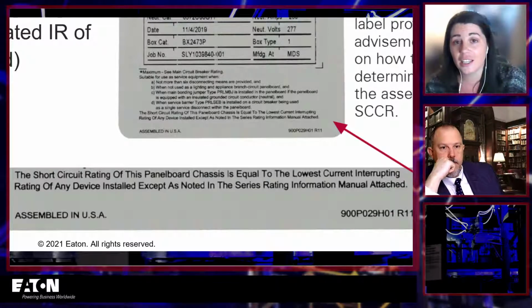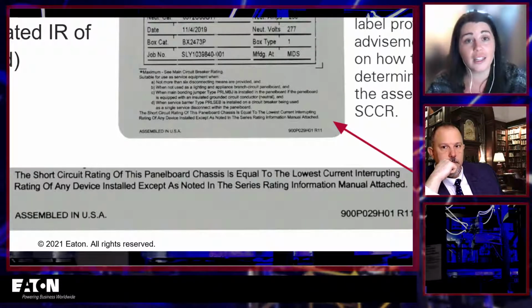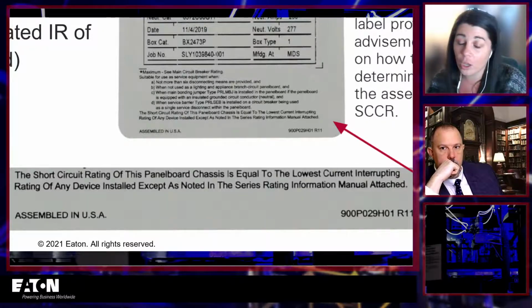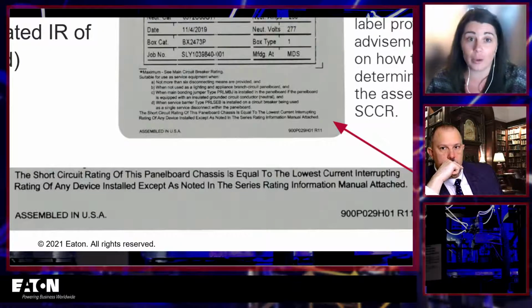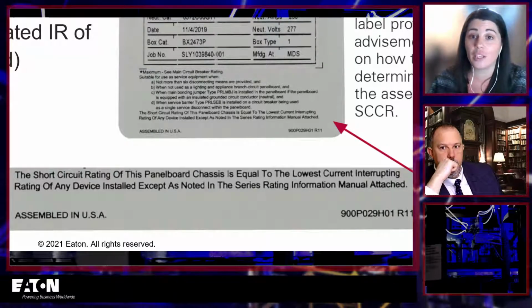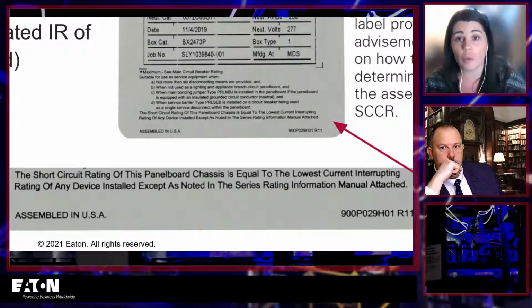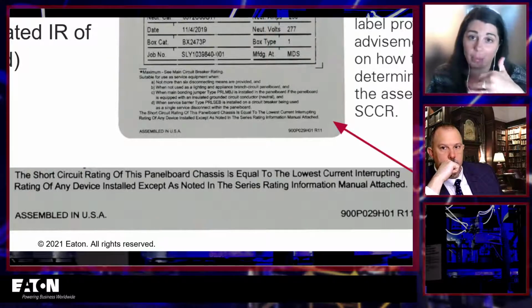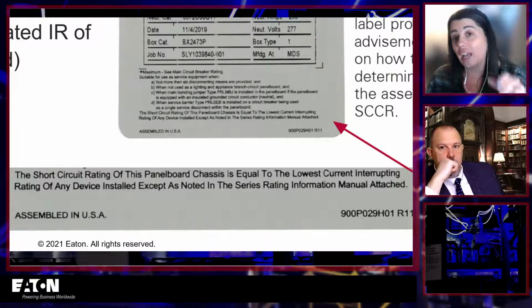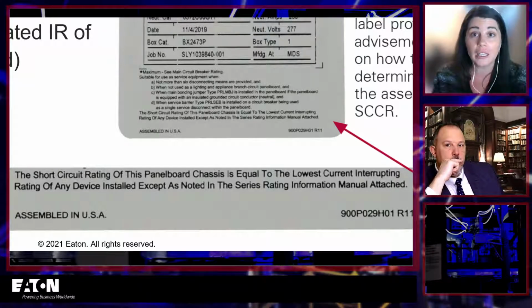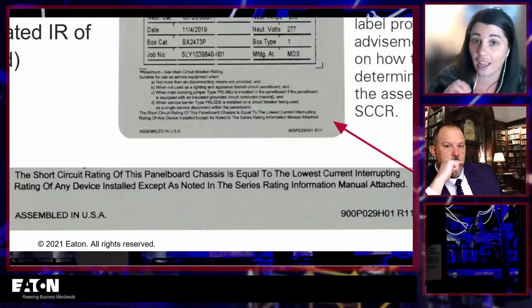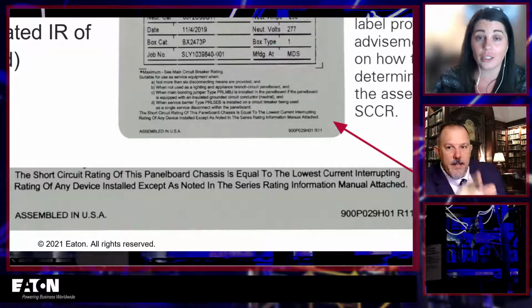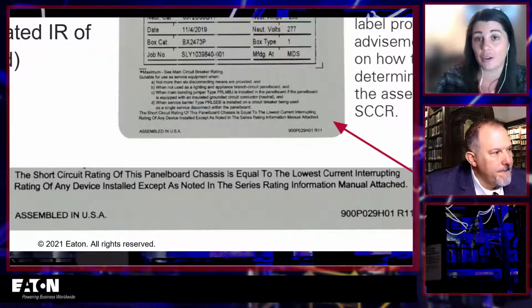of any device installed. So the reason that they do this is because once a piece of equipment like a panel board or a switchboard is installed, there's a lot of modifications that can happen to it in the field. Maybe you take out a breaker and you replace it with a different one. Maybe you had some provisions and spares in there and you just add a new breaker. And if you had a panel board and it was rated 65 kA and then you add an 18 kA rated breaker to it, you don't have a 65 kA rated panel board anymore. You have an 18 kA rated one. So it's equal to the lowest interrupting rating.